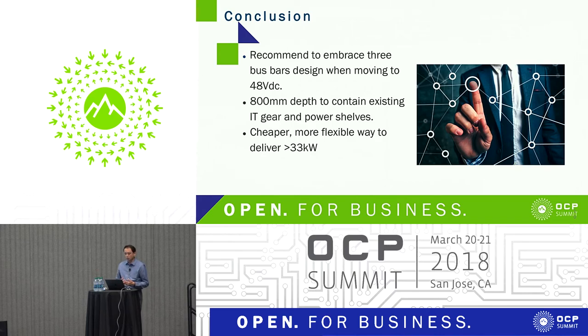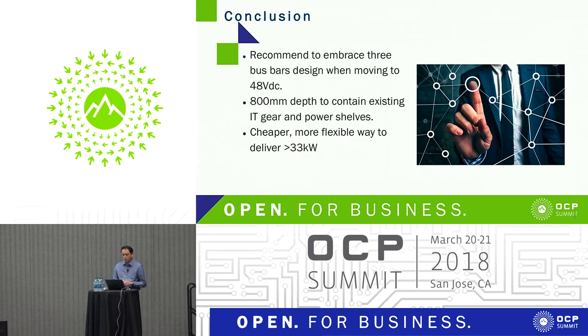In our proposal, we will continue to use the deeper 800-millimeter depth. Servers and storage solutions are becoming deeper, so 800 millimeters provides better thermal management between devices and the bus bar. It will also be much cheaper and more flexible to deliver more than 33 kilowatts — or even further, as we do see more demand for 40 or even 50 kilowatts per rack. It would be more difficult to implement that using a single DC bus bar.